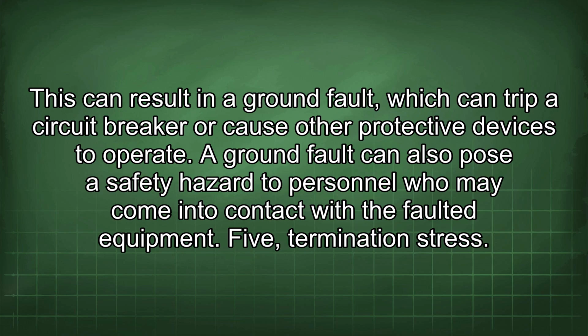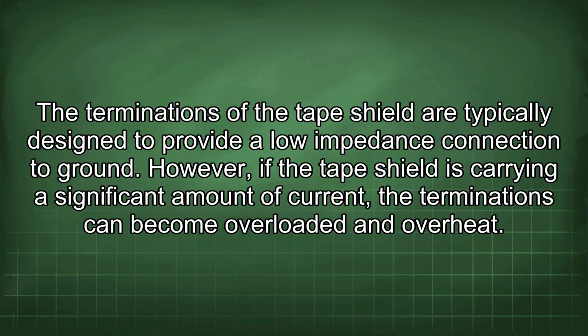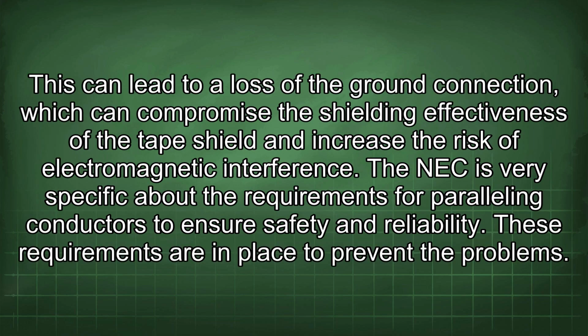5. Termination stress. The terminations of the tape shield are typically designed to provide a low impedance connection to ground. However, if the tape shield is carrying a significant amount of current, the terminations can become overloaded and overheat. This can lead to a loss of the ground connection, which can compromise the shielding effectiveness of the tape shield and increase the risk of electromagnetic interference.